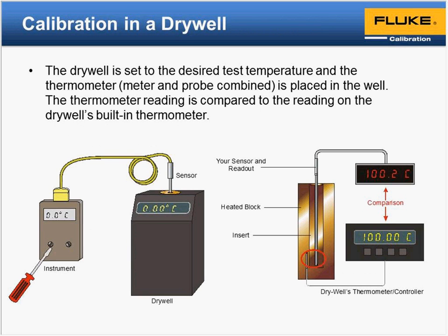We're going to move on to the next level of calibration, but this time instead of simulating, we're actually going to use a source. In this case, we're going to use a heat source. A lot of times you'll hear these termed a dry well, or dry bath has also been thrown around over the years. We also call our newer products metrology wells because we've gone above and beyond what a typical dry well does in that we spec them with axial and radial gradient specs. So you'll hear a few different terms on the sources, but in this case, for the sake of argument, let's pretend our heat source or our dry well is a tool with a 0.05 display accuracy.